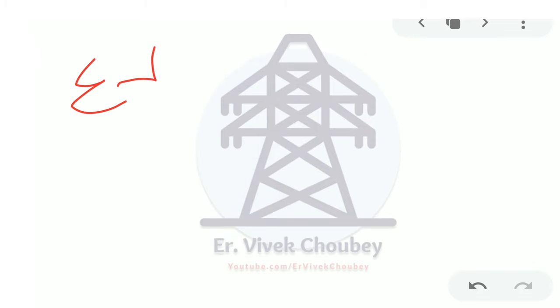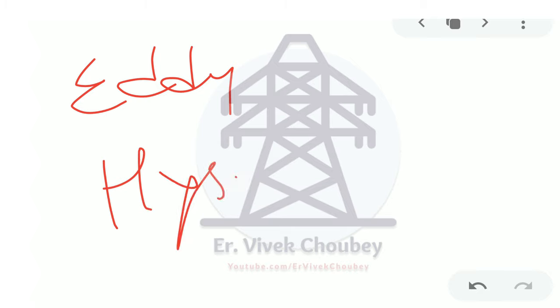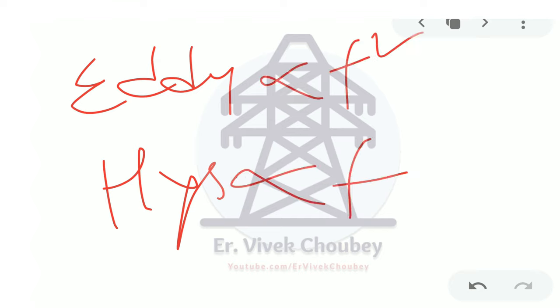Not only that, there are the eddy current and hysteresis losses that we talk about in a transformer. There are various transformers that we use in distribution and in generation. In the transformer, there are these two types of losses, the eddy current and hysteresis loss. Eddy current loss is directly proportional to f squared, and hysteresis loss is directly proportional to f. So these two will also increase, which will be seen as an increase in the temperature of the transformer. Hence the transformer may trip under the sudden increase of temperature. All of these systems are made to tolerate the whole thing only up to a certain limit.